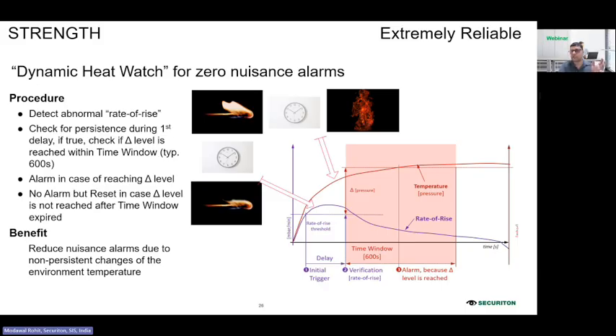It can avoid false alarms from slow or normal temperature fluctuation, which can be from the sun, machinery, or cleaning heat. It detects both rapid temperature rise, which is rate of rise, and critical maximum temperature. It provides early warning of real fire events while minimizing nuisance alarms.